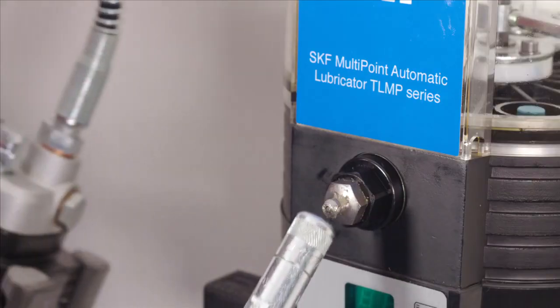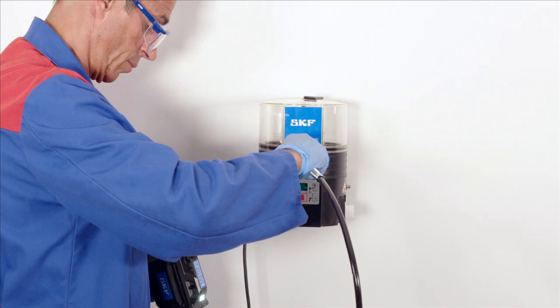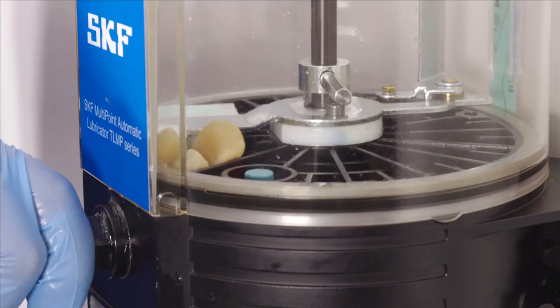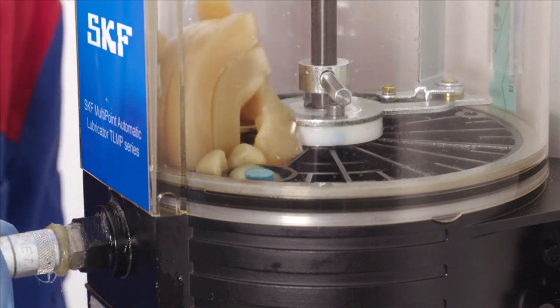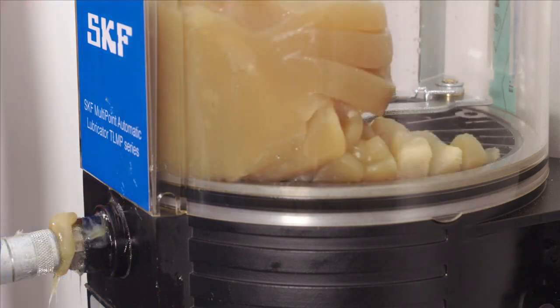The unit can now be filled with fresh grease using either a grease filler pump or a standard grease gun. The grease gun should be applied to the reservoir filling nipple. The total amount of grease necessary to fill the reservoir plus the lower part of the lubricator is approximately 1.8 litres. Fill the reservoir with the fresh grease until the max marking on the reservoir body is reached.